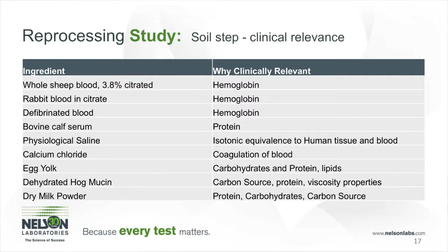Here's a list of all of the soil ingredients and why they are clinically relevant. I presented this information to FDA in 2011, and we have not been asked about our soil determination since then. We also have been getting information from our clients on deficiencies that other manufacturers have had from the FDA, and we are finding that they're even recommending the test soils we utilize in the validation. So it's great news for us because we've written a lot of information on the justification of why we choose the test soils that we choose and ensure that they are simulated use test soils.